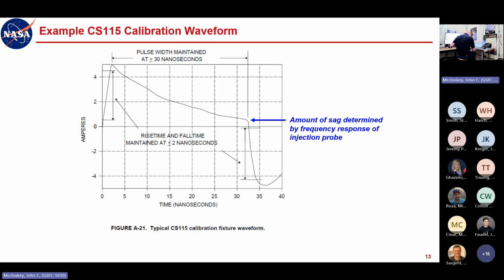I have one probe here. I don't think I'm going to hook it up in the interest of time, but one of the first probes that we hooked up to just test this out has a low frequency of 5 megahertz. The full frequency range for CS114 is 10 kilohertz to 200 megahertz is what we test to, but most of these probes actually are rated up to 400 megahertz. So they go down to 10 kilohertz. But with some of the older probes, like when CS114 was first introduced, you generally had two different probes, one for the low frequency range and one for the high frequency range. So this one starts at 5 megahertz.